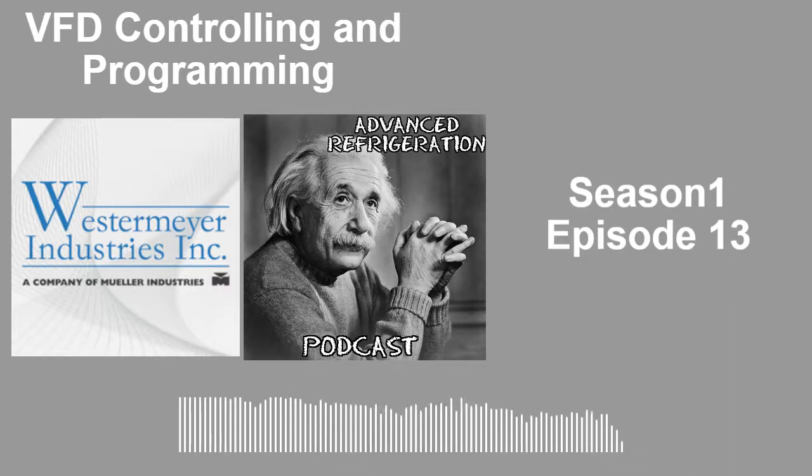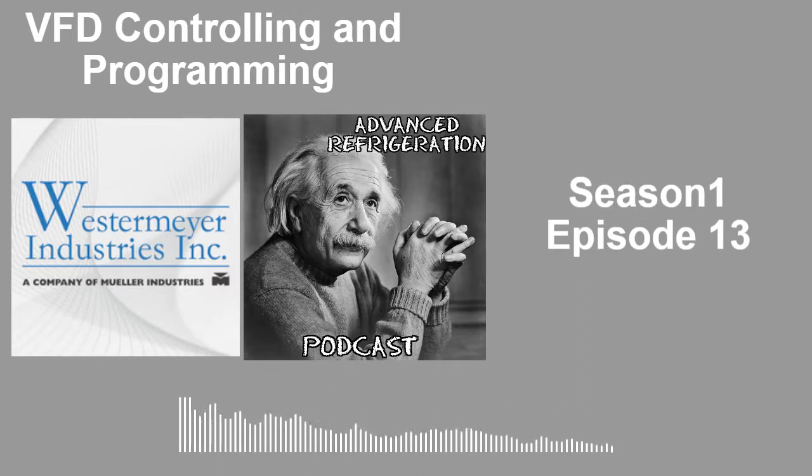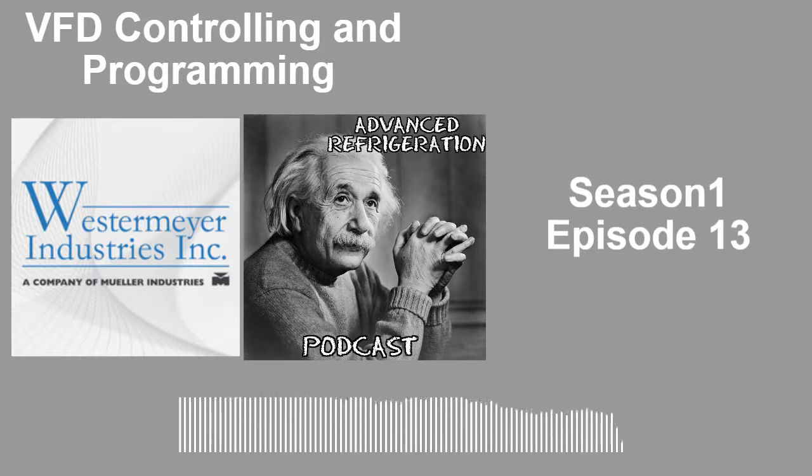With the enable, though, back to that real quick. Sometimes it's not just closing 2 sets of contacts. Sometimes you have 1 set of contacts. Sometimes you have to jump potentially 3 sets of wires together, because some drives have a forward and reverse command with them. So if you were enabling, I think NIDEC has forward and run enable that you'd have to jump together with the 24 volts DC that's actually on the drive to make it ready, where it doesn't say inhibit, where it's actually not ready.